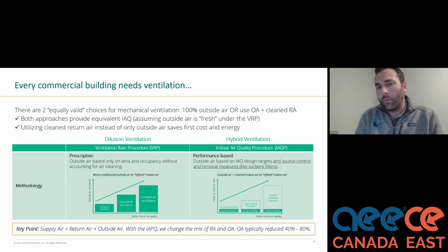Moving on here, what this means is that historically we've looked at dilution to ensure good indoor air quality. So you look at the ventilation rate procedure and you see that the VRP and its prescriptive approach, if you want better indoor air quality, you need to increase the amount of ventilation that's going on. However, the market is quickly pivoting to a method of hybrid ventilation. And hybrid ventilation is using filtration, using source control and removal as that proxy for outside air.